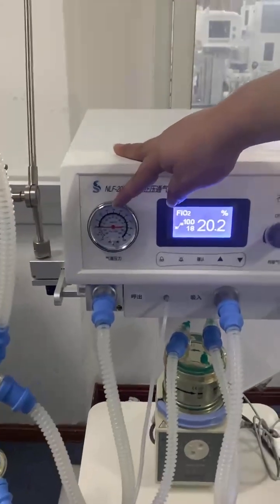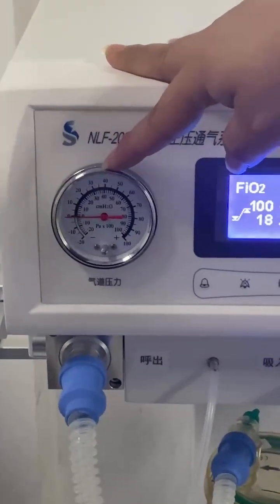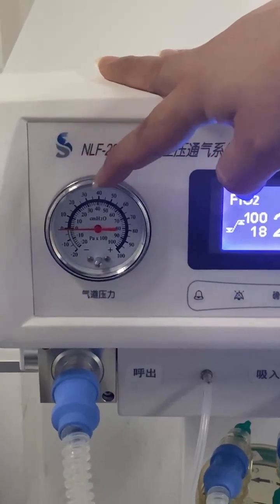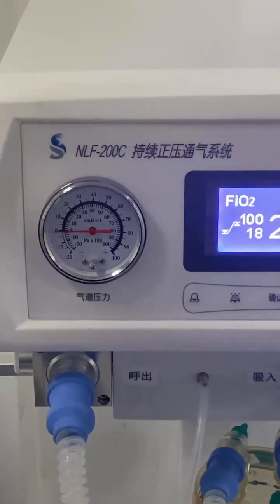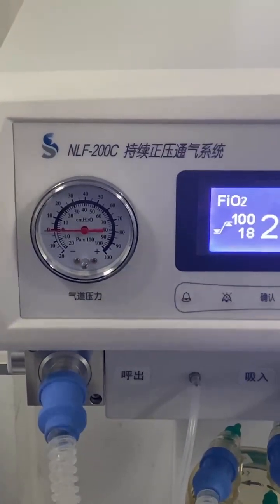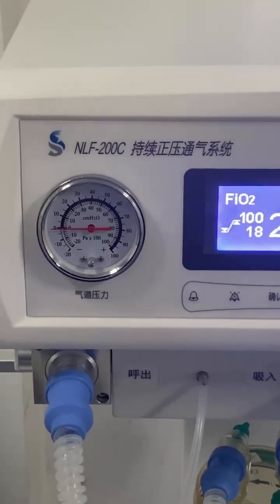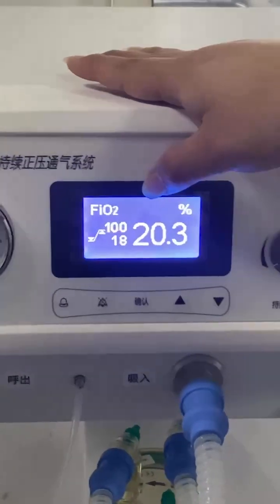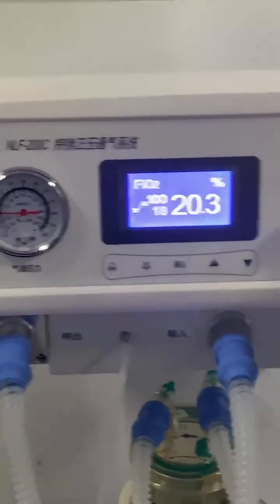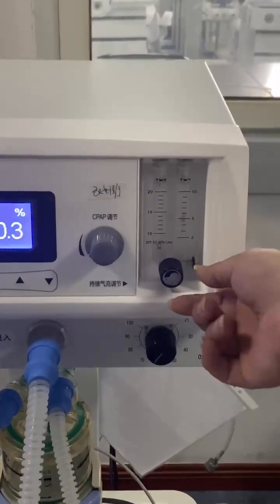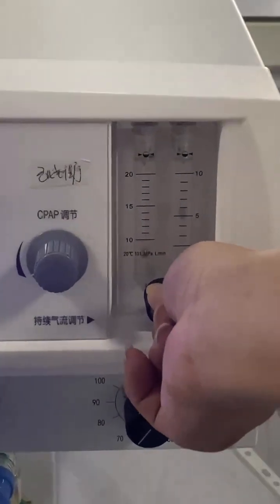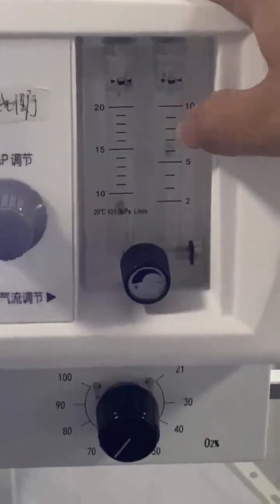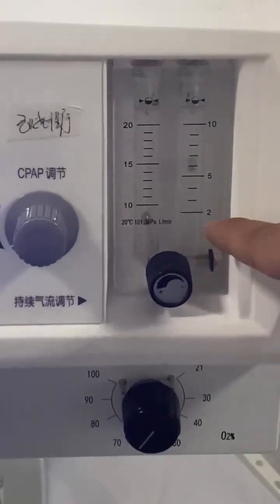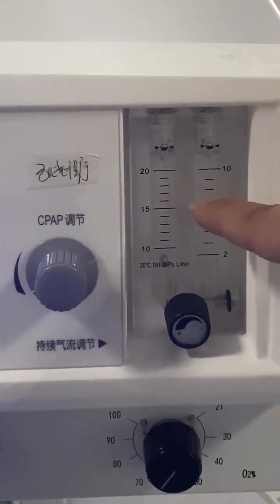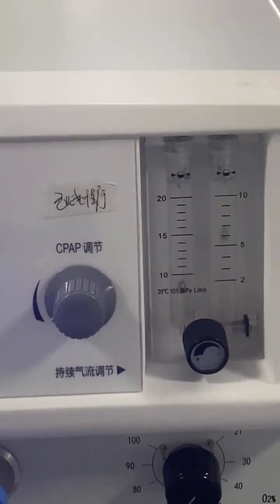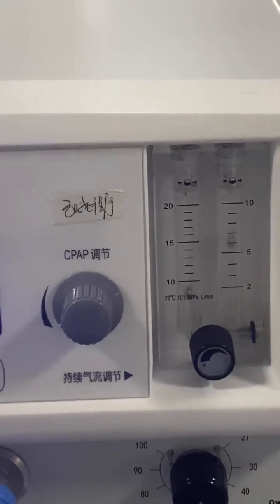For this pressure gauge here, this one is for you to monitor the airway pressure, and from the airway pressure we can know the patient pressure and how the patient is using, and if we need to increase or decrease the pressure or the parameters. And the oxygen concentration will be shown on the screen directly. Then from here we can see there is the flow meter, and for this one we can set the flow, and as you can see by the mechanical flow meter here, the range can be 2 to 20 liters per minute. So actually it's already a very wide range for different kinds of neonatal, including the pediatric.